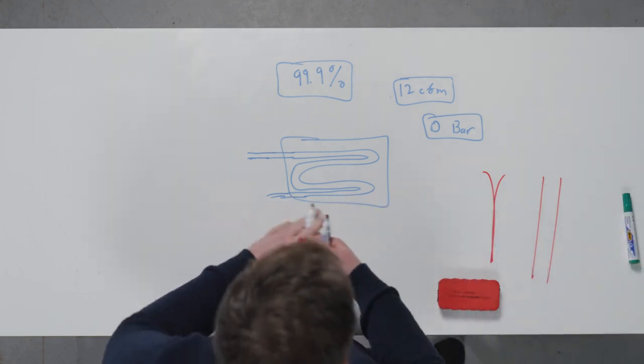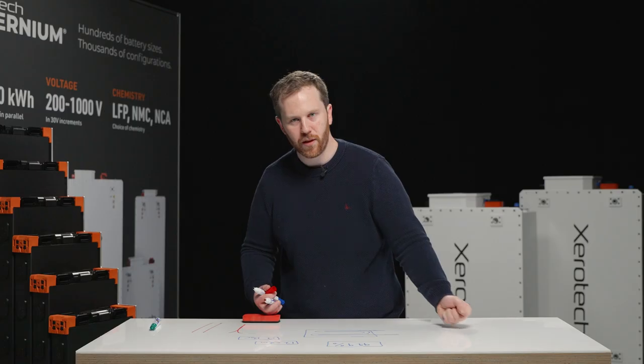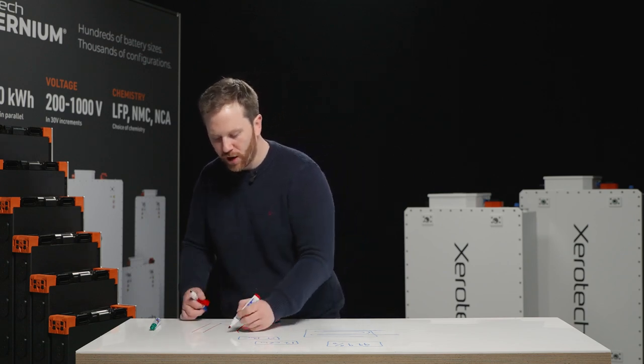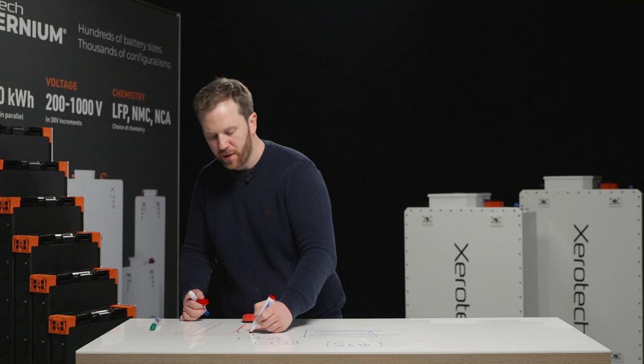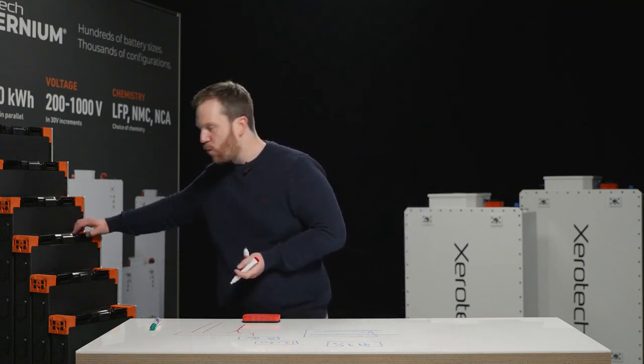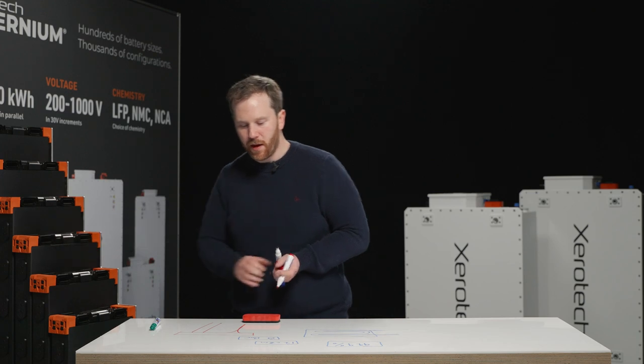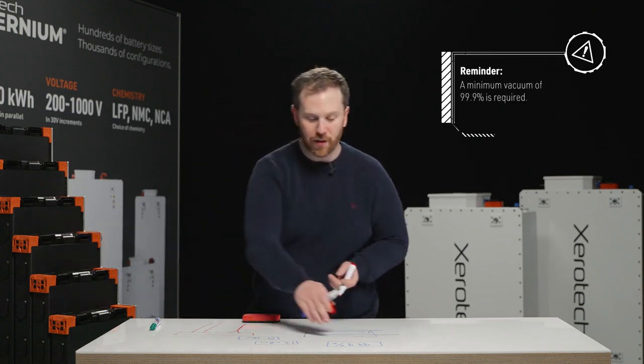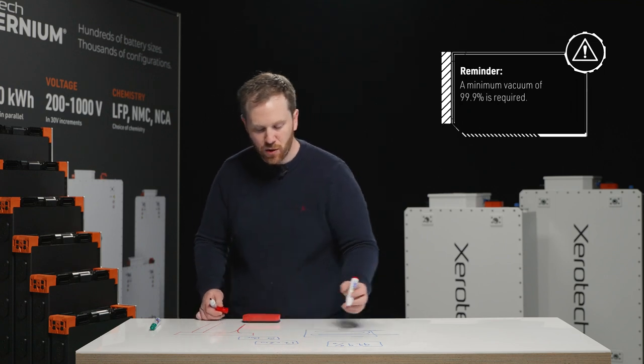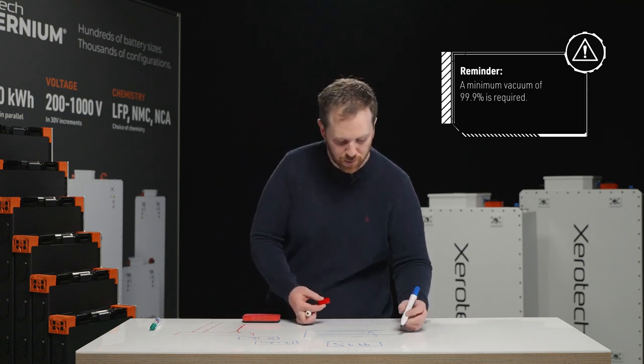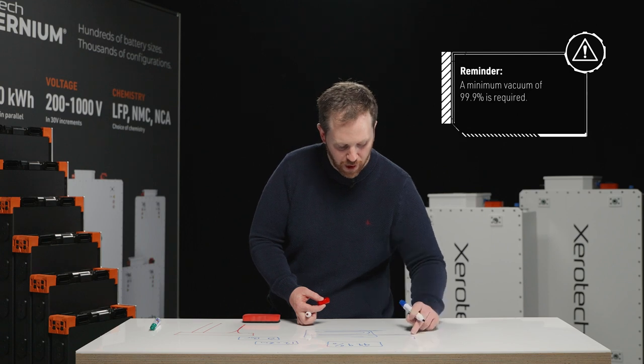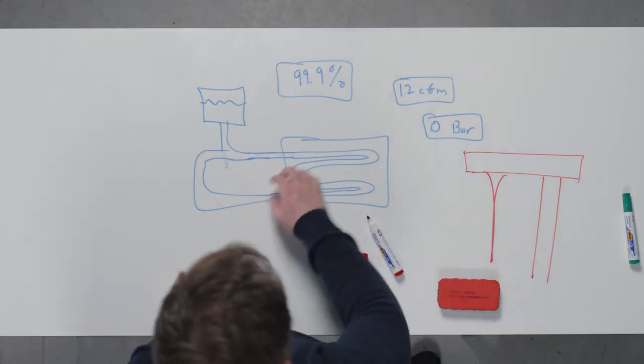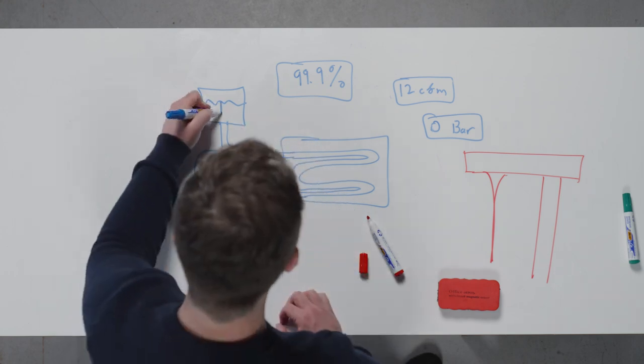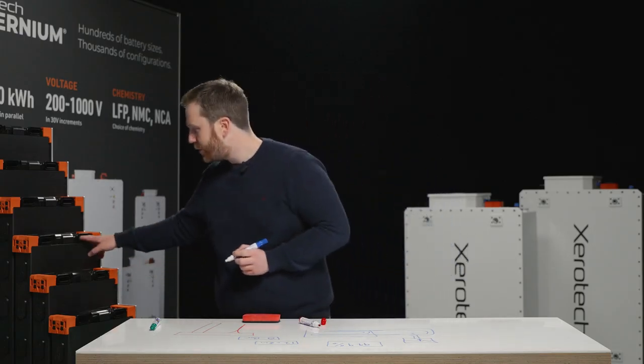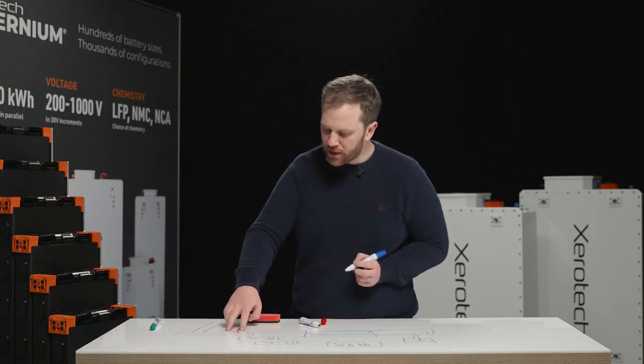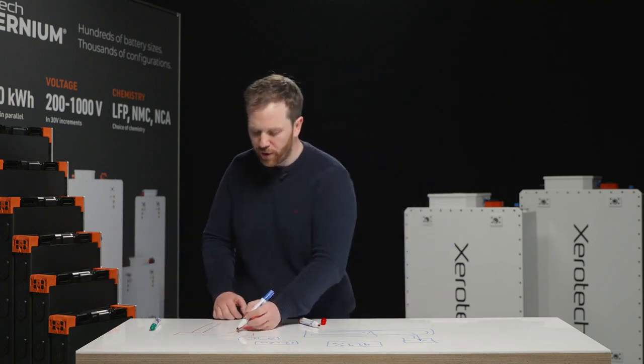And when you let the system draw in the coolant into the system, it's only going to draw it in to the areas that are naturally open and self-supporting. For example, the rigid plastic headers here in the system. For you to fill up the entire system, you need to have it at a full vacuum, and then you need to, when you're driving water into the system, so for example, this would typically come out of a header tank. What will happen here is that once you release the vacuum, it's going to suck some of the coolant into the system here, because these volumes are going to stay open under vacuum, but it's not going to fill the ducts because the pressure will have equalized here.